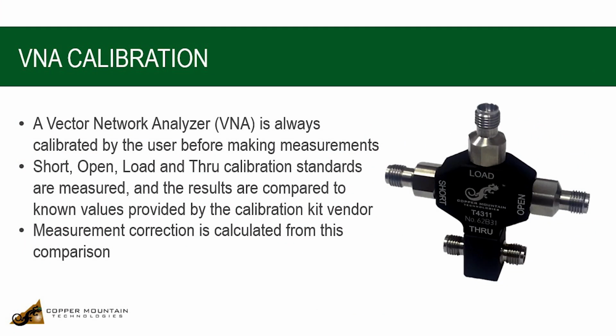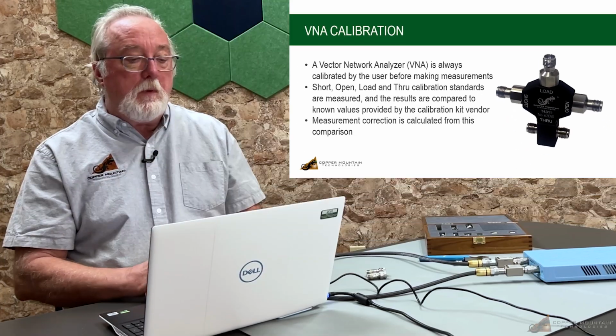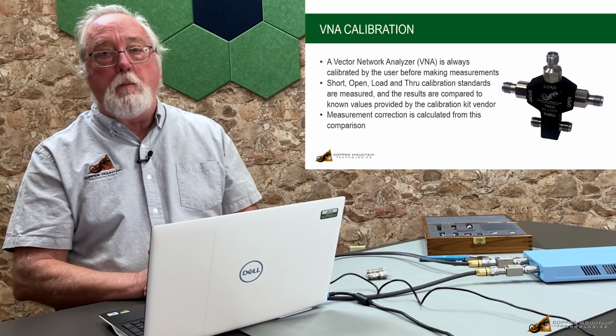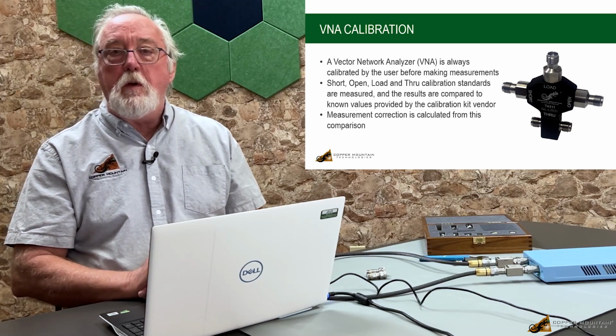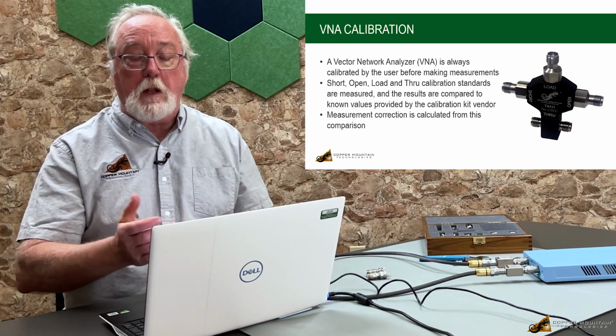For calibration, a vector network analyzer, a VNA, is always calibrated by the user before making precision measurements. Short, open, load, and through calibration standards are measured, and the results are compared to known values provided by the calibration kit vendor. Measurement correction is calculated from the comparison between the measured and the known values of the calibration kit.